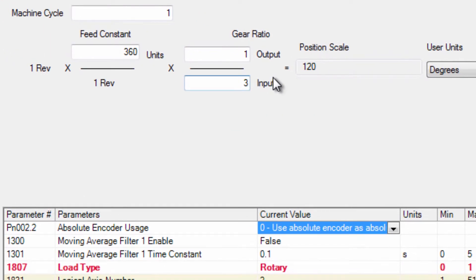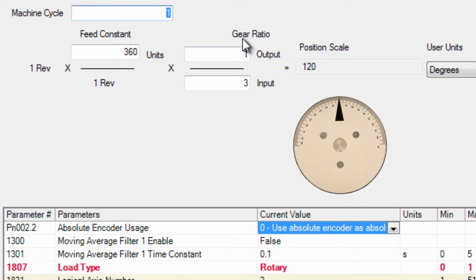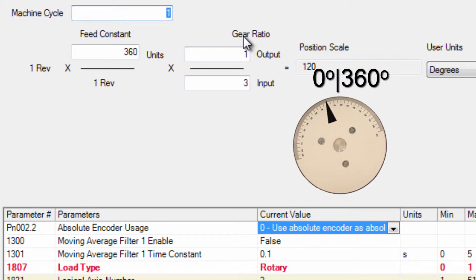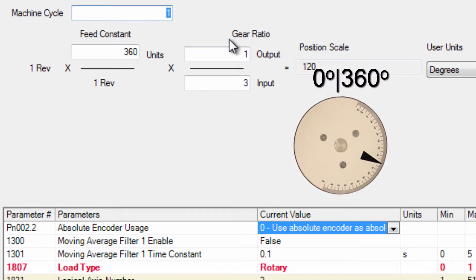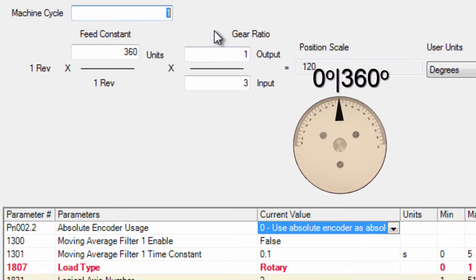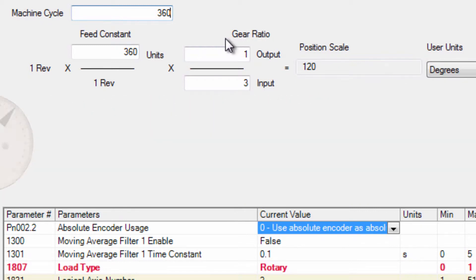This axis is a rotary load and so we do have to set the machine cycle. Rotary load means that the load is able to move infinitely in one direction eventually arriving at the original position after one machine cycle. So at 360 degrees the table is back to position 0.